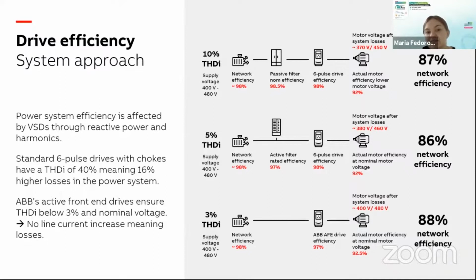Here you can see several examples on the screen. In the very first case, we have a pretty efficient drive having 98% efficiency, but its effect on the power network and total system efficiency is such that the system efficiency is about 87%, because to mitigate the power quality effect the drive brings, we need to employ different kinds of filters, and those bring their own losses to the system.